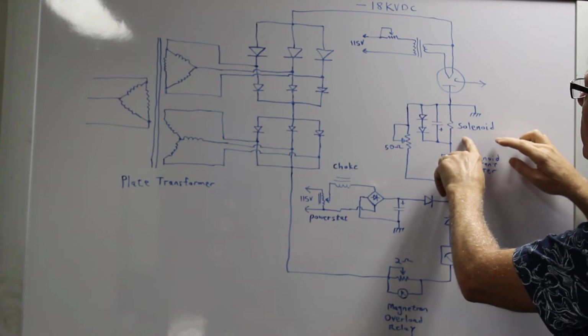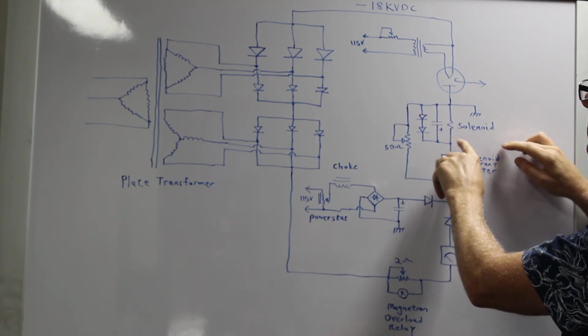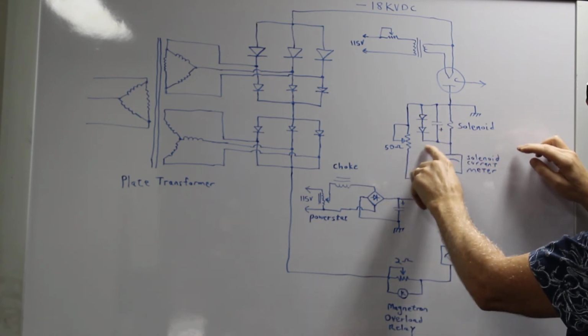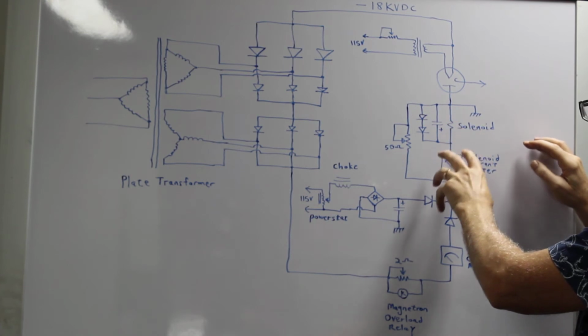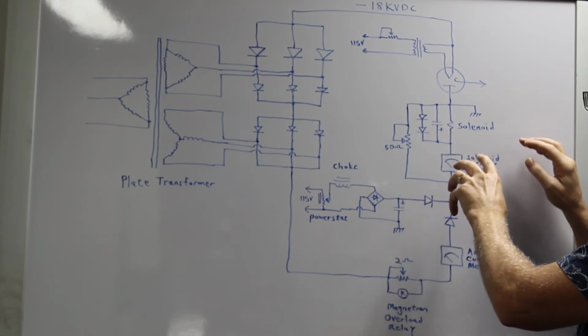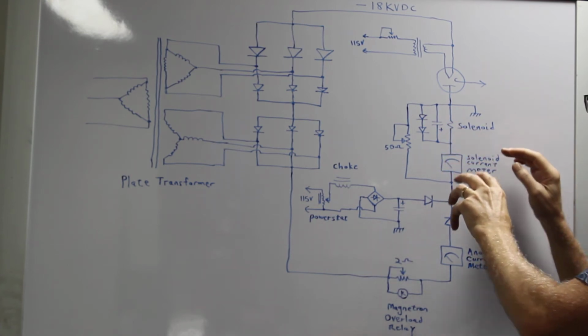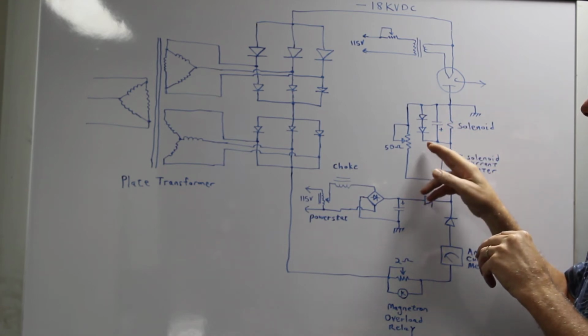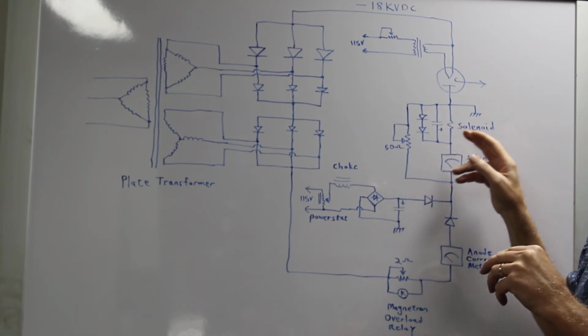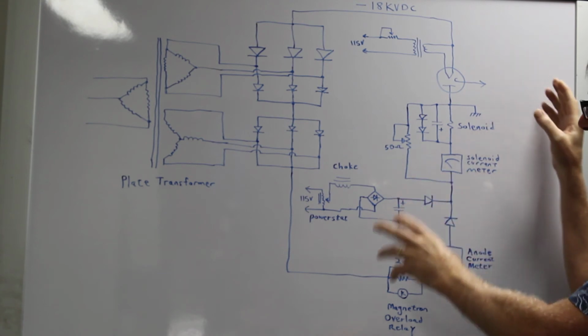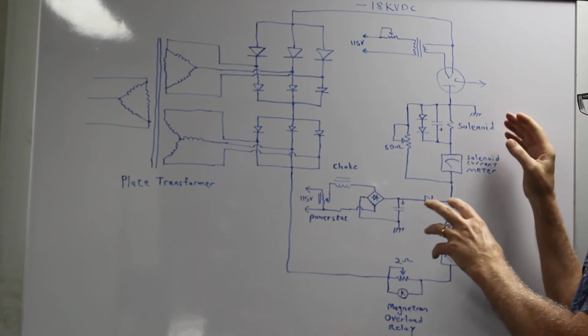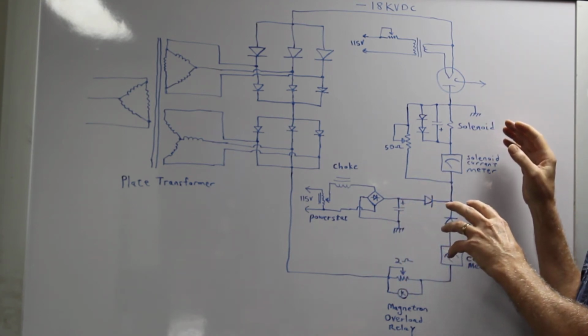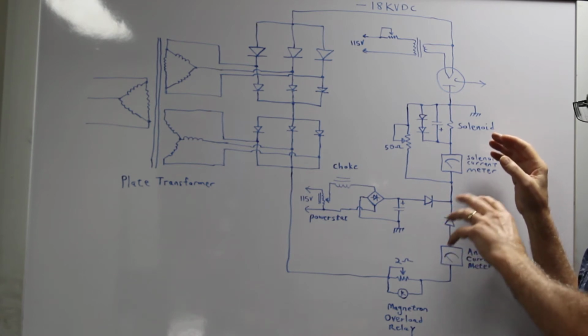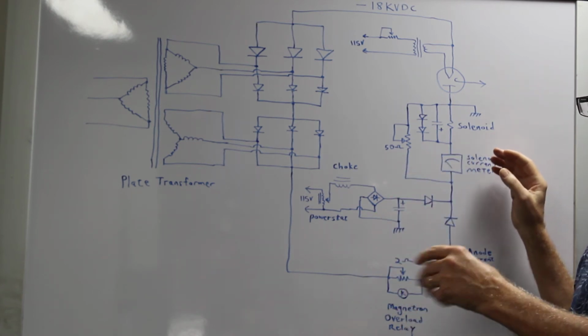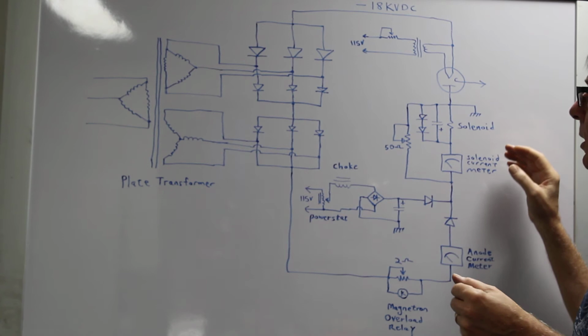The solenoid is represented here, and there's a couple of diodes and a capacitor in parallel with the solenoid, and these kind of swamp the solenoid. Sometimes they're called flyback diodes, and what that is for is to protect the solenoid itself and the external circuitry from a high voltage pulse if the solenoid power is shut off unexpectedly, like if the whole machine is kicked out from a breaker opening somewhere.